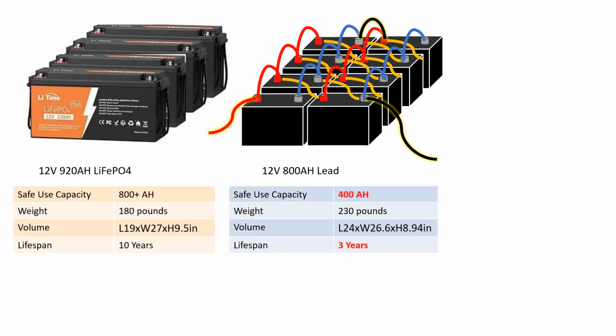So with the lithium iron phosphate, our safe use capacity is going to be around 800 plus amp hours, up to that 920. The weight, because they are significantly lighter at 45 pounds each, is 180 pounds for all 4 batteries. The volume is pretty comparable from lead to lithium, but the lifespan is 10 years for lithium iron phosphate. The same set of batteries, or the same rating in lead, would only give us a safe use capacity of 400 amp hours at 230 pounds of battery. The footprint's about the same, but their lifespan is only 3 years.